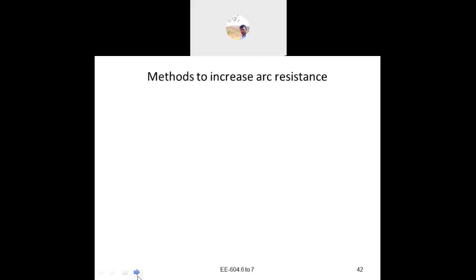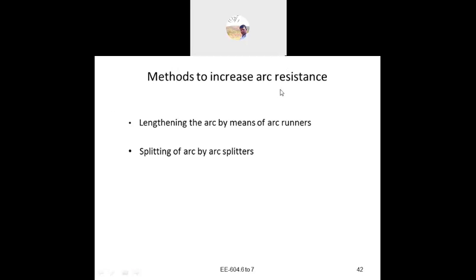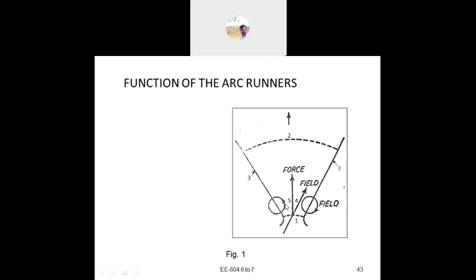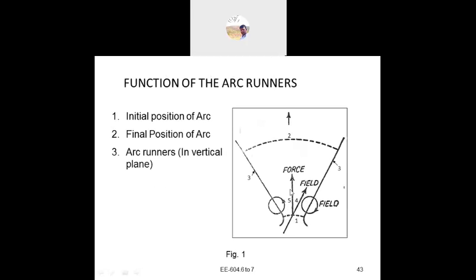Next another method. To increase the resistance: lengthening the arc by means of arc runners, splitting of the arc by an arc splitter, and cooling of the arc. You can see the two contacts and the arc is formed with the current flowing. Arc runner, you can see the initial position here, and here is the final position of the arc. When the arc is produced in this line, the arc runner will move the arc like this. At the last stage, the arc will be quenched.